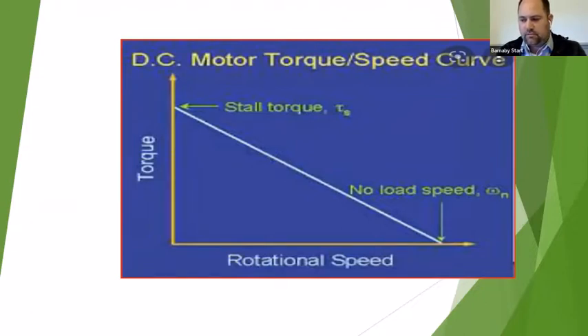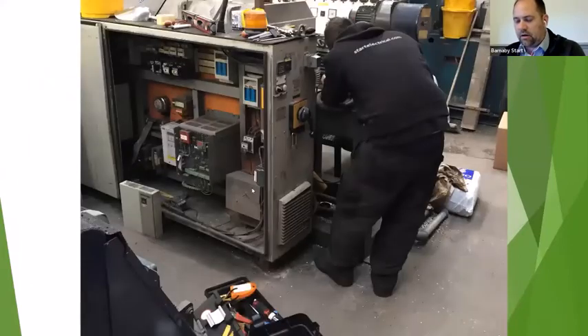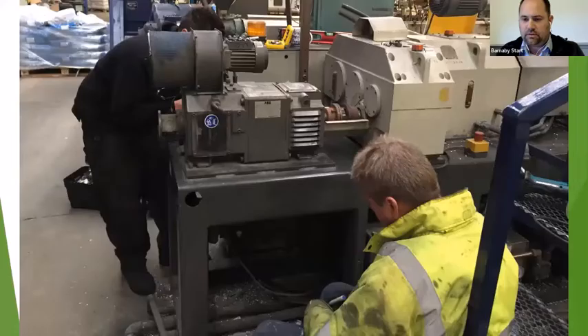Some applications, we had one application where it was something like a 180mm extruder. It's quite a big extruder, and they were using recycled PVC, and the torque requirement, even when it's hot, was probably 150%, if the barrel was left for any time with material in it. So the torque requirement on this particular extruder, it would pull tons and tons of amps to break away. So it does depend on the extruder. The ones in the pictures that we were looking at generally are okay. They do need sufficient torque to break away.